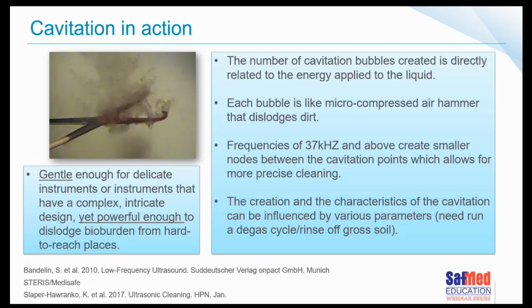Rightio. So we said cavitation in action. The number of cavitation bubbles created in that liquid is directly related to the energy applied to the liquid. So that's why it becomes quite important to understand your device itself, because the energy applied in hertz will differ depending on what it's designed to clean. So in industrial settings, you might have one that works at 400 hertz, and that perhaps is too much for what we need in our environment. So each bubble, like we said, is like a micro-compressed air hammer that ends up dislodging the dirt. And frequencies of 37 kilohertz and above create smaller nodes between the cavitation points, and that allows for more precise cleaning.